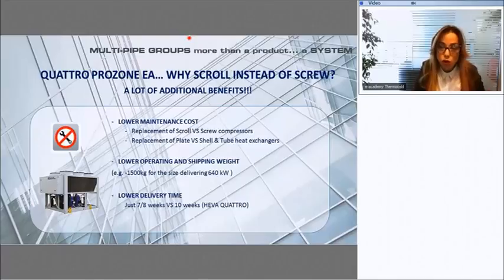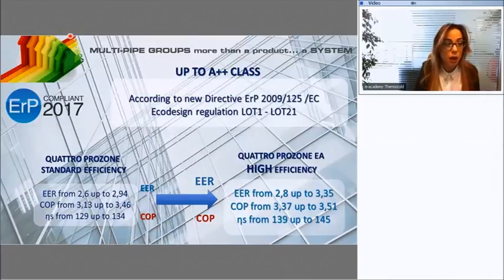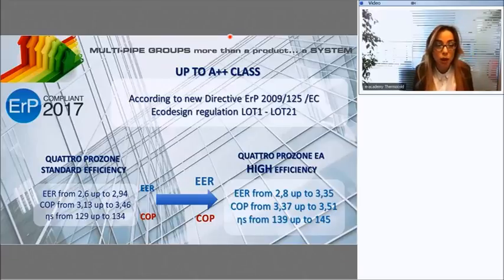Other advantages of the scroll solution are lower maintenance costs. Think about the replacement of a scroll compressor compared to the replacement of a screw compressor. Of course, it's much easier and quicker to replace a small and light scroll compressor than a big screw one. And also think about the replacement of a plated exchanger compared to the shell and tube exchanger. So it's clear that choosing a multi-scroll solution ensures lower maintenance costs.